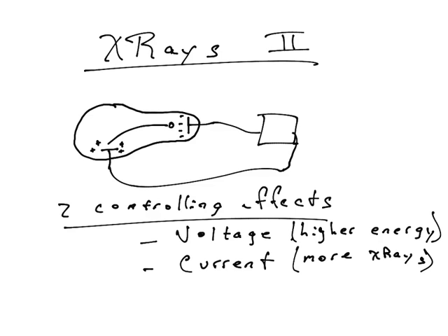And in order for an X-ray to penetrate into a material, it has to be of higher energy. So an X-ray technician can increase the voltage of the X-ray machine, allowing the electrons to be more attracted. They move faster, they have higher energy, so when they collide with the plate and create an X-ray, that X-ray will be of higher energy.